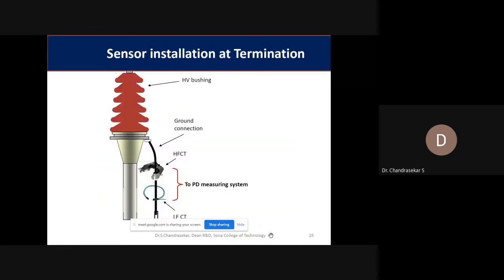So this is the HFCT sensor installation in the terminals. Okay, normally the ground is connected in the ground connection, and the top portion is the high voltage bushing, and this HFCT sensor and the LFCT sensor both are connected in the ground leads. Through that it will be connected to the PD measuring system, and further it will be communicated with the substation operator.